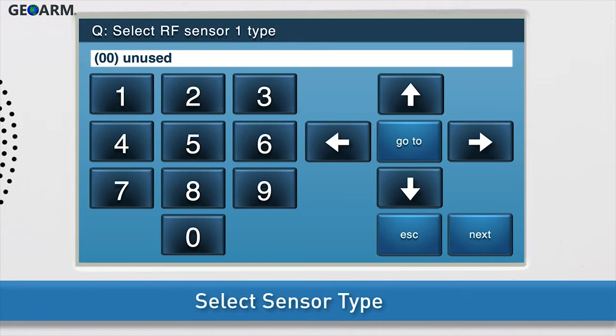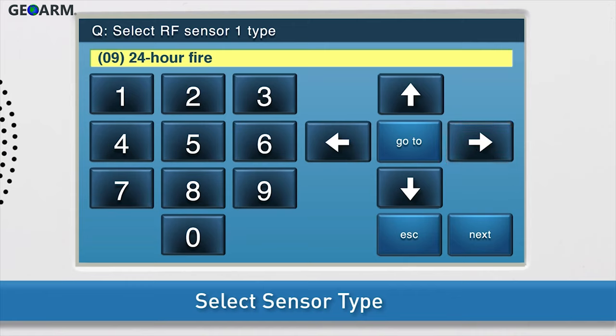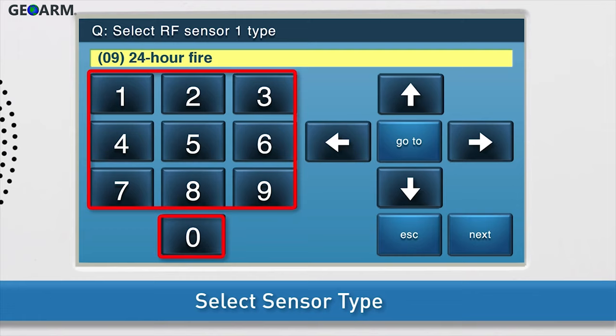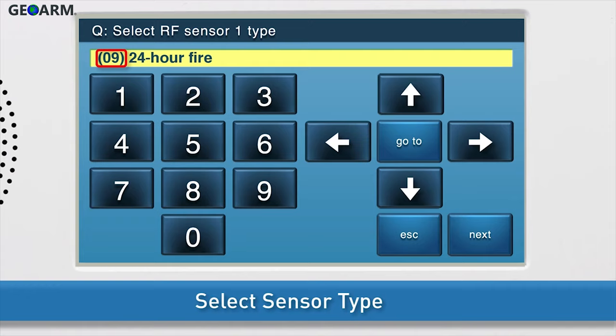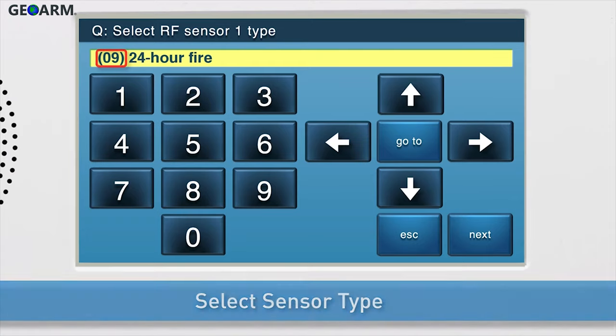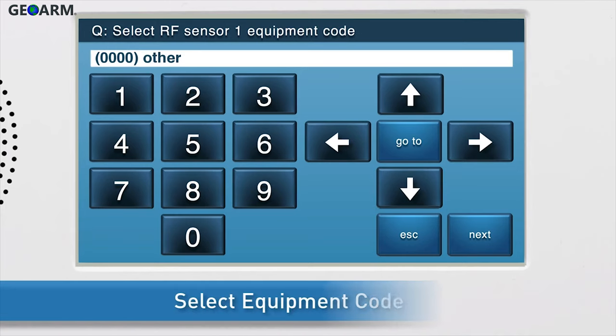Select the sensor type. There are two ways to change the sensor type. Option one, press the right arrow until 24-hour fire displays on screen. Option two, use the on-screen keypad to type zero, nine, which is the two-digit code for the 24-hour fire sensor type. Press the down arrow to go to the next sub-question.